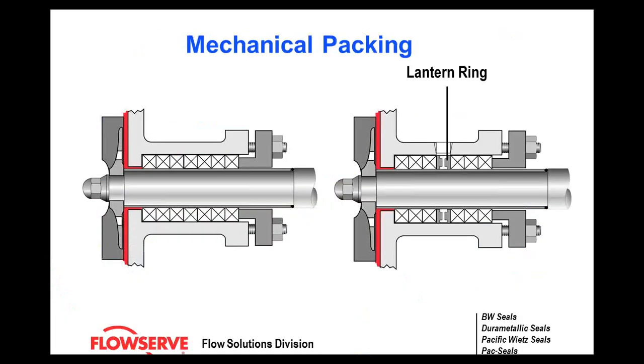Before mechanical seals were developed, the typical way to seal a pump was with packing — a fibrous material usually impregnated with a lubricant like graphite, cut into sections and stuffed down a stuffing box. A packing gland was then applied on the back side to tighten everything down. One thing to note: packing is in direct contact with your shaft, whether riding directly on the shaft or on a sleeve, and therefore it will rob horsepower.